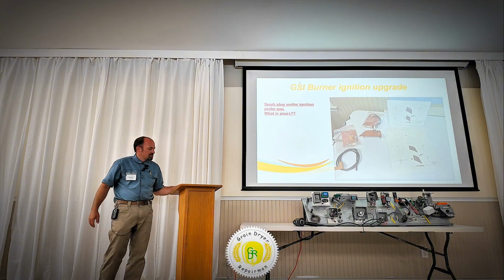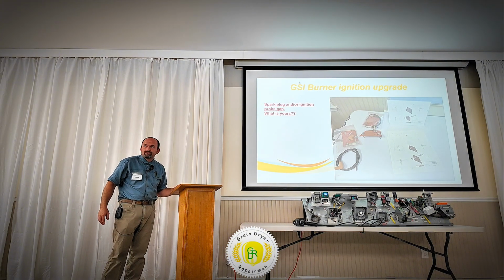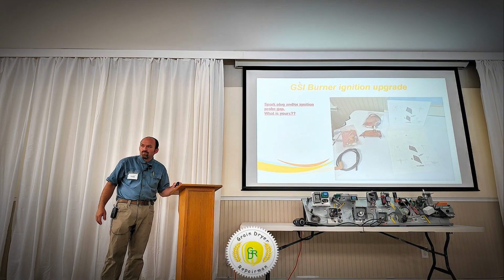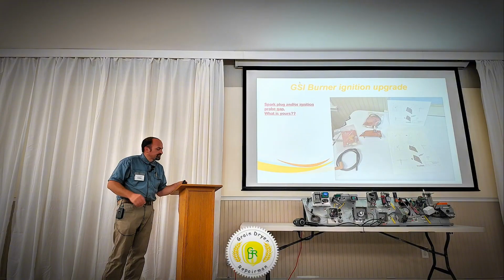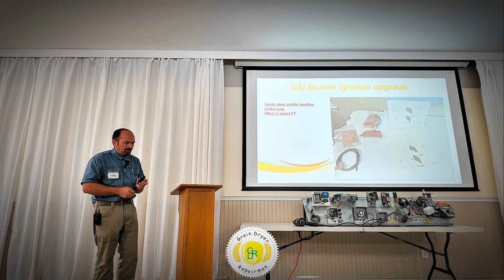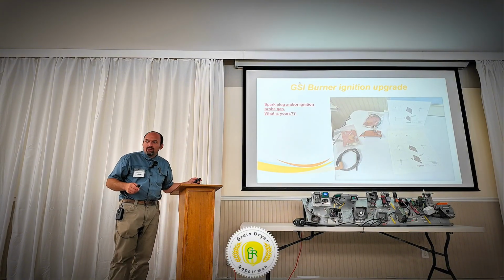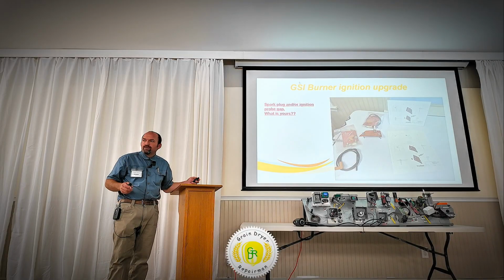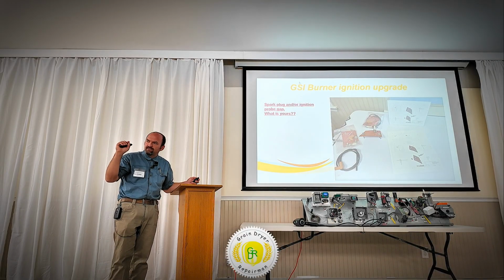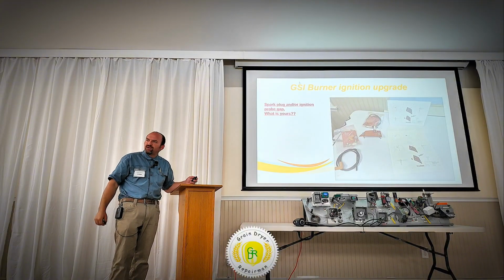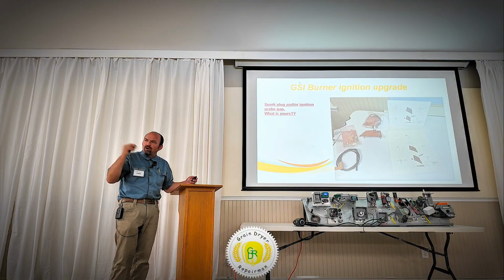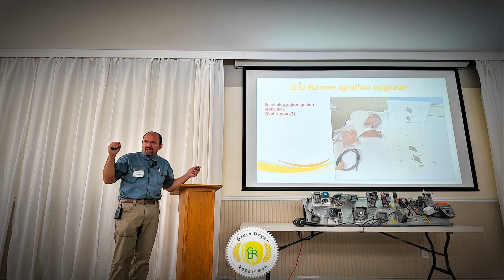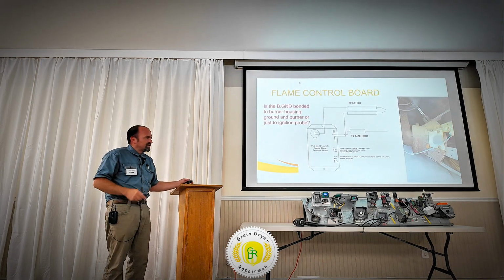What if a maintenance manager has a GSI dryer with a Fenwal board and puts in that ignition upgrade using an Autolite 64 spark plug - does that work the board harder? No, as long as the gap is right, it should be fine. It's no different. The gap is what makes the difference in how hard that transformer works and how much heat it generates - it's the gap of the arc. So if that gap is 1/8 to 3/16, it's going to work the same.